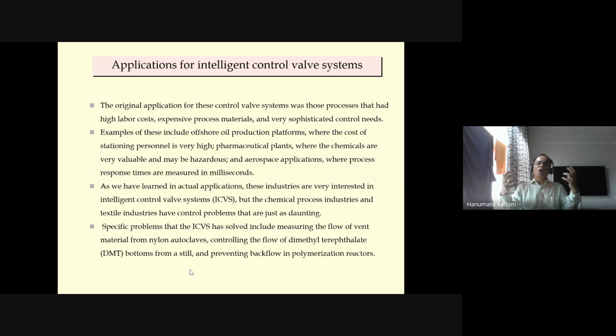Second, expensive process material, like oil and gas, very expensive, and very sophisticated control needs, because sophisticated control needs means you require accuracy, safety, reliability. All these needs are required for those applications, and normally it is required on offshore and onshore platforms. So mainly this focuses on oil and gas, onshore and offshore applications. Applications include the offshore oil production platform, where the cost of stationing personnel is very high. Then the second application is pharmaceutical plants, where the chemicals are very valuable and maybe hazardous, pesticides and all. And aerospace applications, where the process response times are measured in milliseconds. So accuracy is important in airplanes.